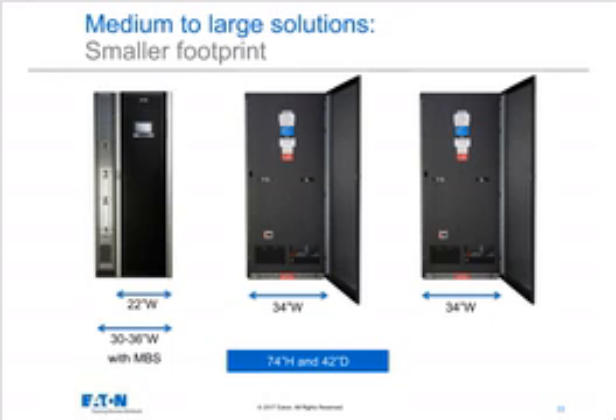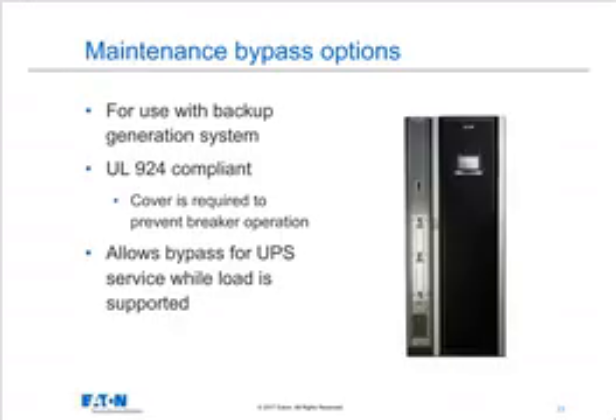What about a maintenance bypass or a wraparound bypass? This is something we recommend with most of our three-phase UPSs, and the reason it's there is to allow the service person to work on the UPS with the entire UPS completely de-energized for safety while still providing power to the output and the mission-critical loads on that output.